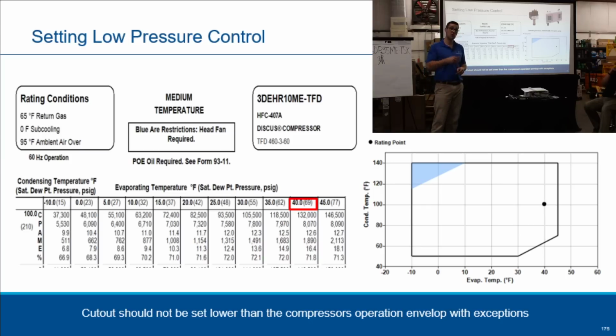Killing it. It's starting to, right? Higher compression ratio leads to higher what? Heat, right? More work. So now your customer's paying more money as well, right? If you want, one of the rules of thumb is to start with 10 degrees below. So if you're running at 40, start with 30. But what do you have to check for? Not superheat. What happens if I only set it to 30? What happens to the pressure? Really quickly.